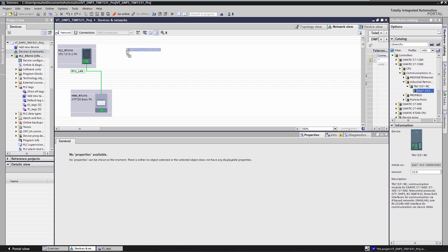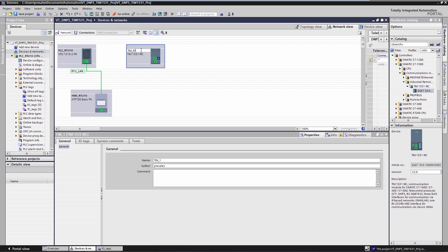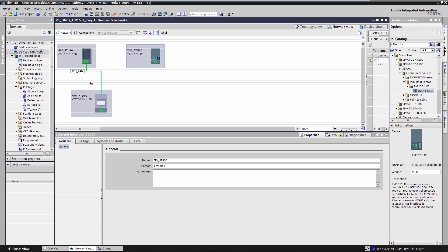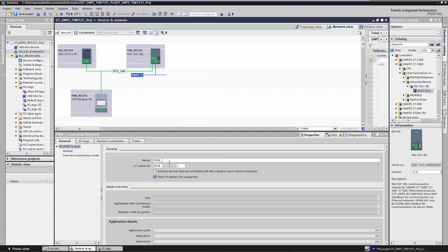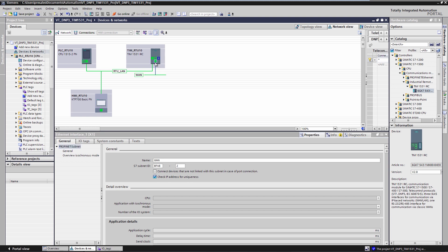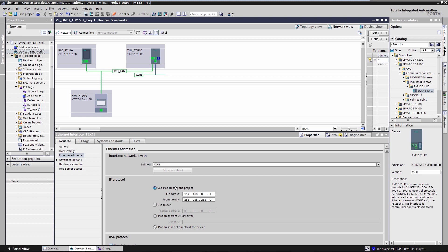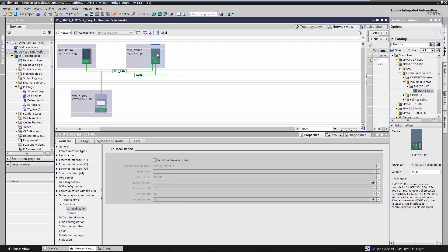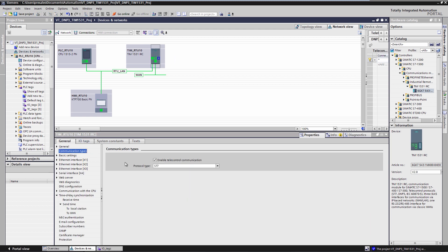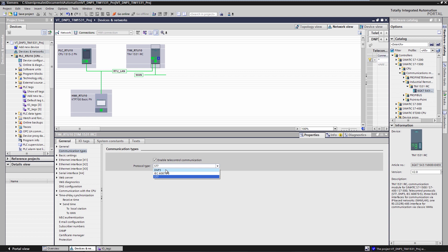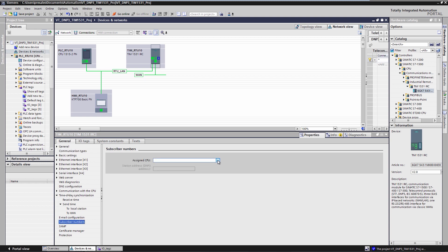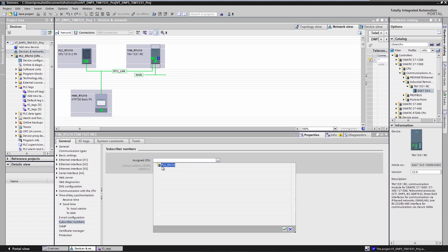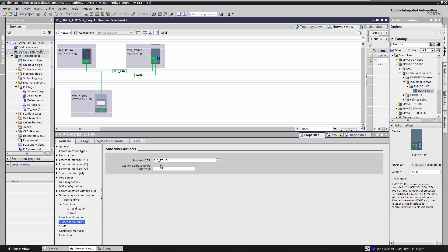First, I add a TIM 1531 IRC and connect it to the Ethernet port of the SIMATIC. Then I also connect the TIM with a WAN for communication with the DNP3 master. Next, I configure the IP address with which the TIM or the DNP3 RTU communicates with the master. This is the IP address 192.168.100.10. Now I select the communication protocol, DNP3 in our case. I assign the TIM module to the SIMATIC S7-1500 CPU. The TIM and the CPU thus form a DNP3 RTU within the TIA portal project. Then I configure the DNP3 address of my RTU. It is DNP3 address 10.